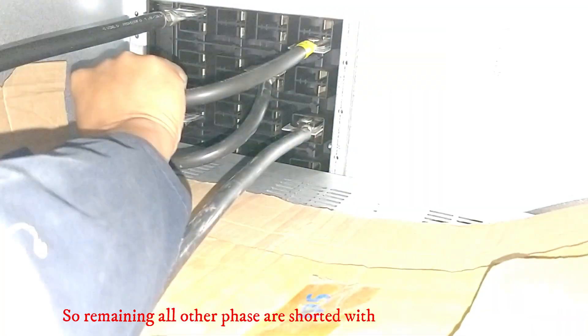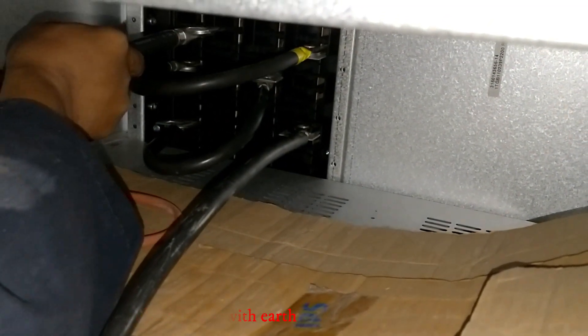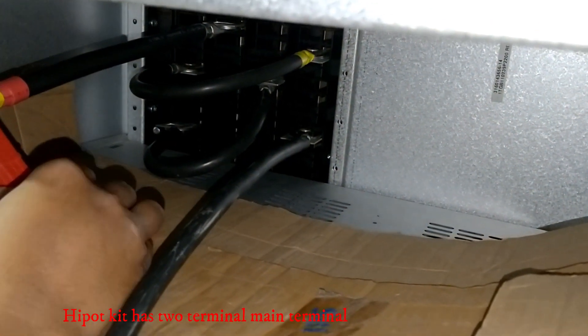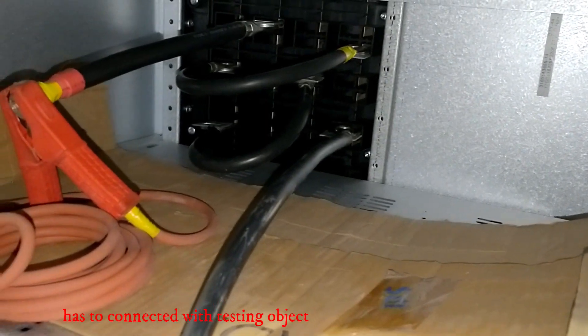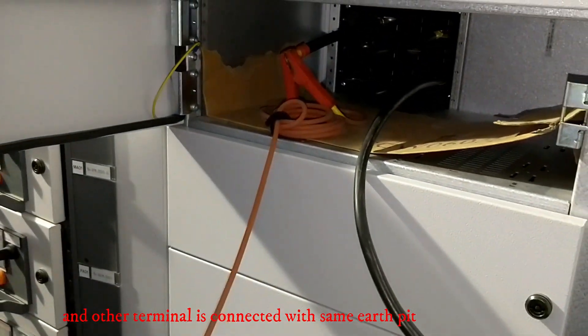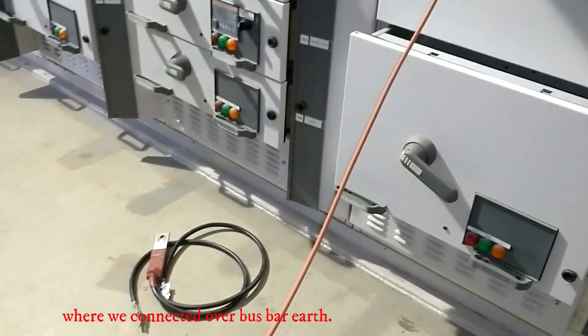First, I am going to do hipot test for R phase. Remaining all other phases are shorted with neutral and connected with earth. R phase is connected with hipot kit. The hipot kit has two terminals — the main terminal is connected with the testing object, and the other terminal is connected with the same earth pit where we connected the bus bar earth.